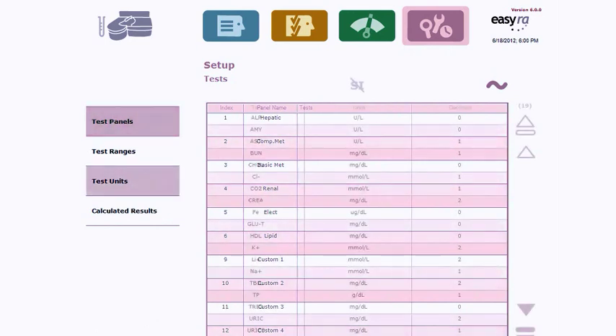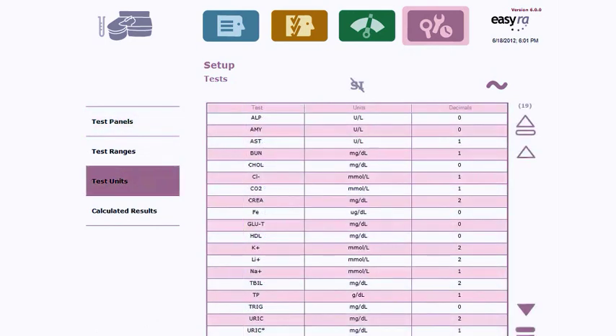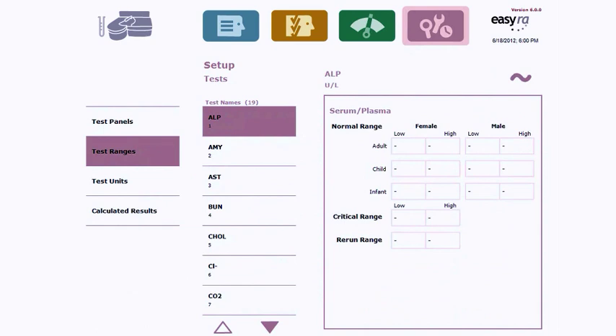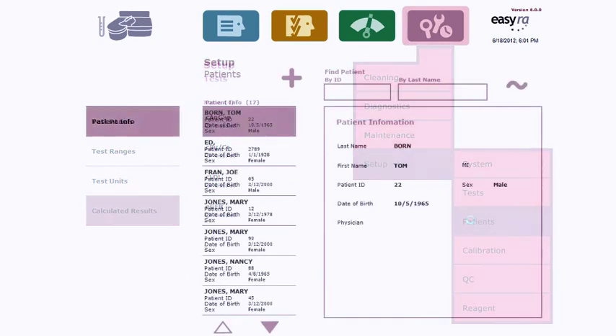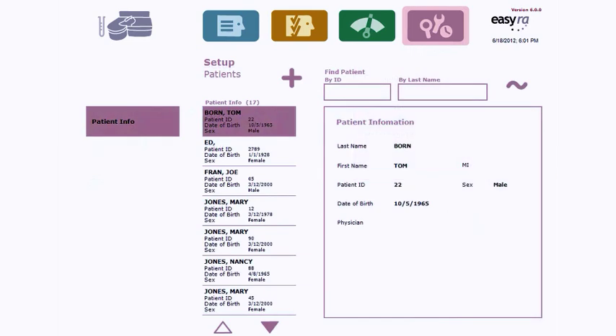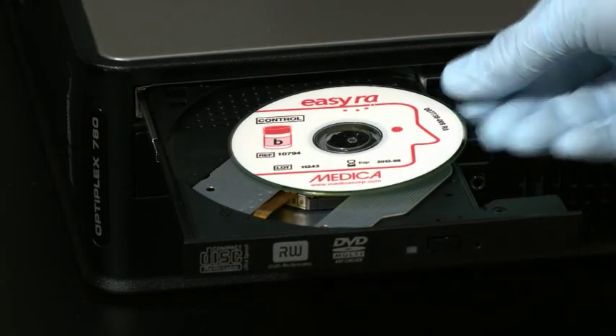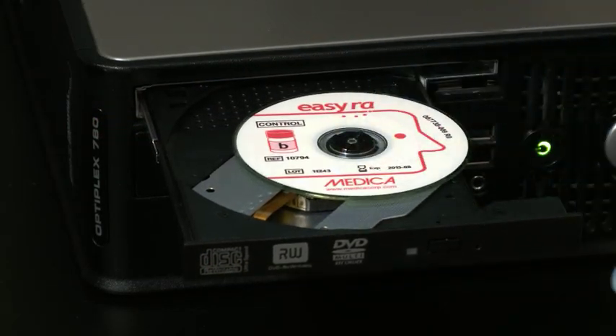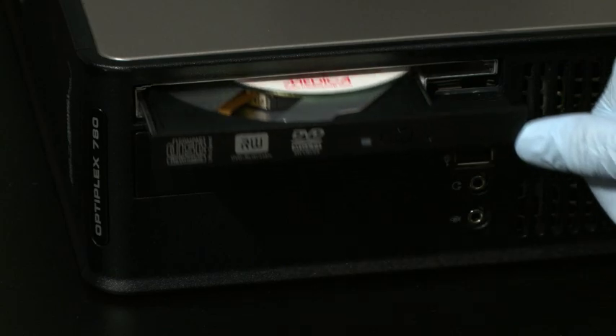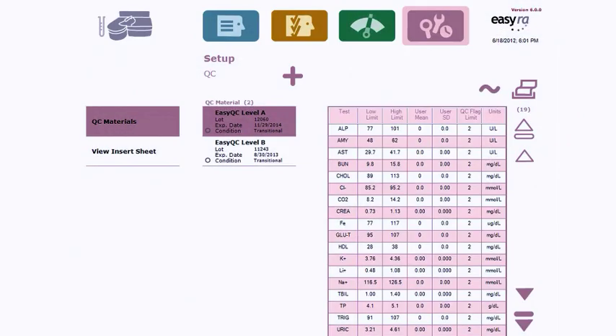Configure and maintain your analyzer from one friendly menu. Set up custom test panels and units of measure, as well as normal and rerun ranges for various ages. A comprehensive database allows you to input and store patient demographics. Conveniently download all calibrator and QC parameters from a CD, or choose to enter the information manually.